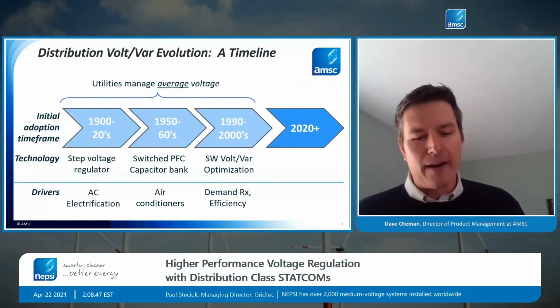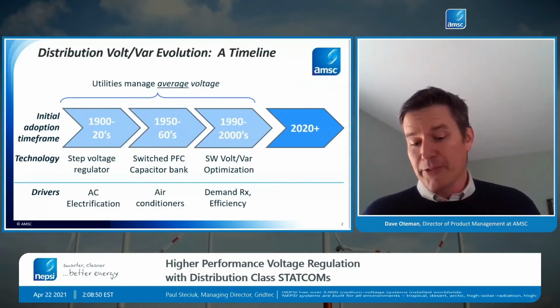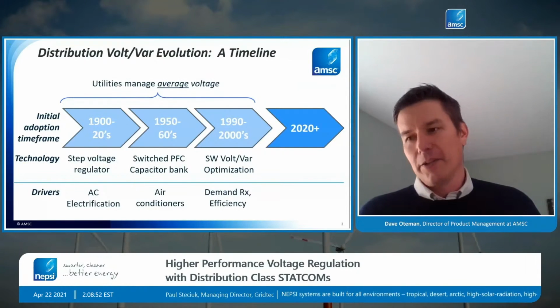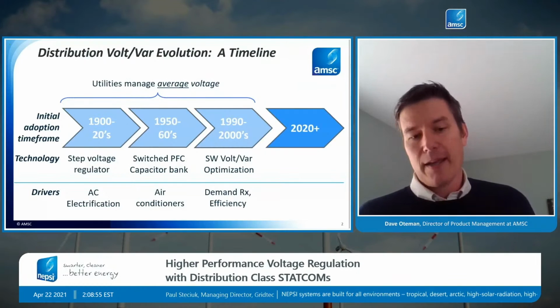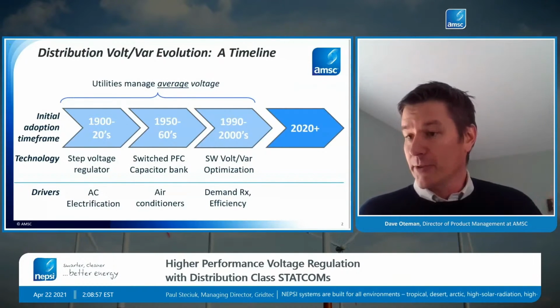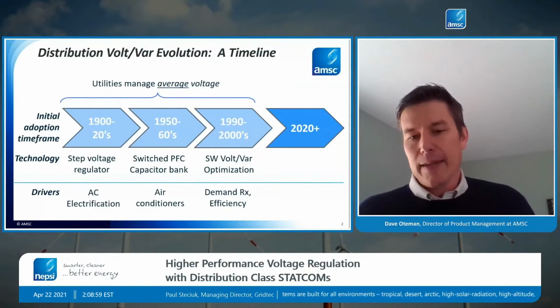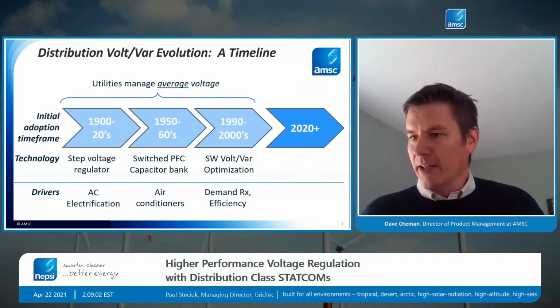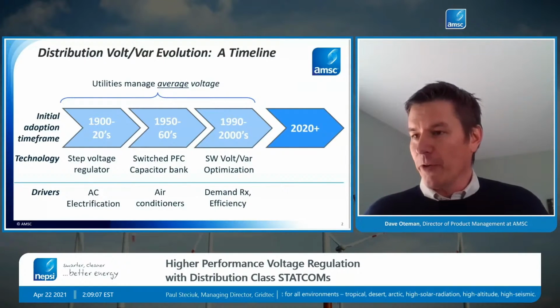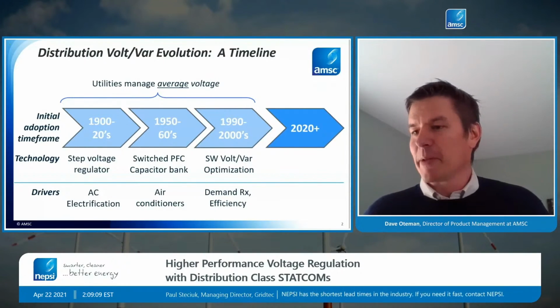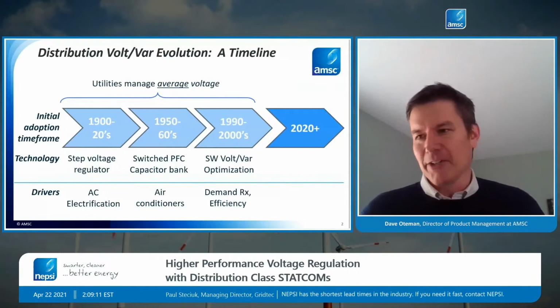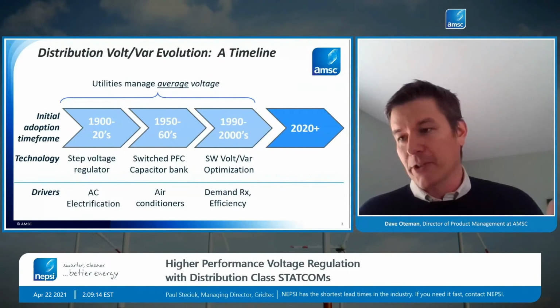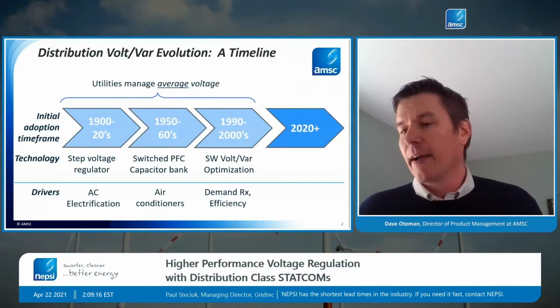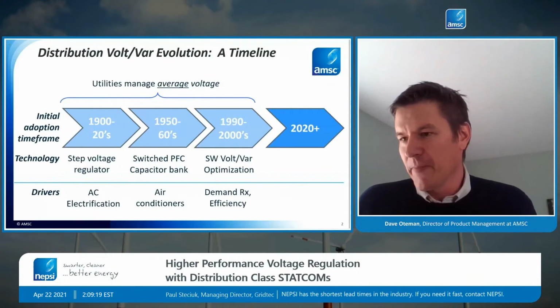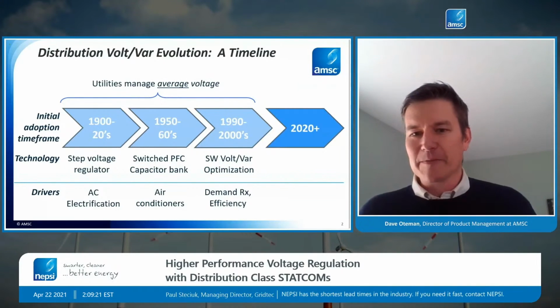The big benefit there was really being able to reduce peak demand. You reduce peak demand and you get to defer large transmission investments, for example. And then also efficiency — we can get our kilowatt-hours required down by running the voltages more flat and more optimally across large portions of the distribution system. We still see these deployments growing today; there are still feeders moving towards this software automation of capacitor banks and line regulators.